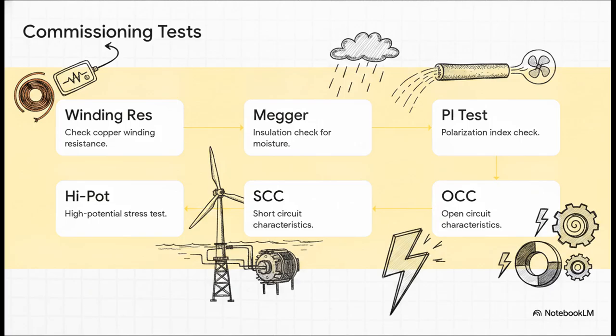You start passively, measuring copper winding resistance, and then moving on to Megger and PI tests to hunt for any moisture. Only when that machine is proven completely 100% dry do you even dare spin it up for open and short circuit tests. And finally, you hit it with the ultimate trial, the high potential stress test. And you really need to know these pass criteria by heart. Things like achieving greater than 100 megaohms on a new Megger test, or seeing absolutely zero breakdown during a high-pot test. That high-pot test is the ultimate stress test. You're applying twice the rated voltage, plus an extra 1,000 volts, for 1 full minute. If the insulation holds strong without breaking down, congratulations, your machine is finally ready to sync to the grid.